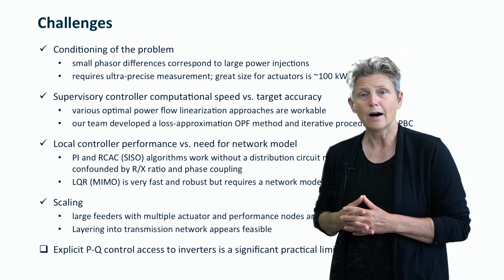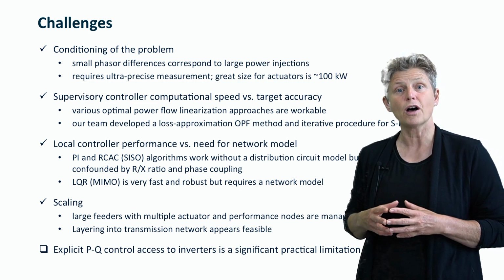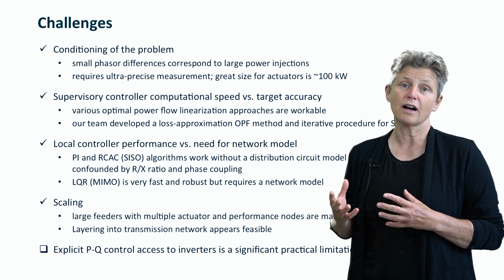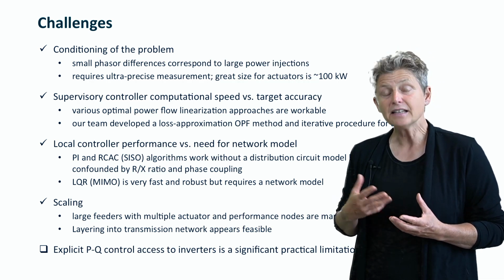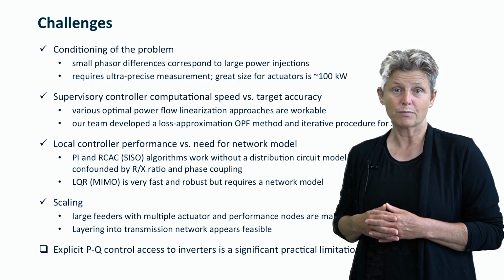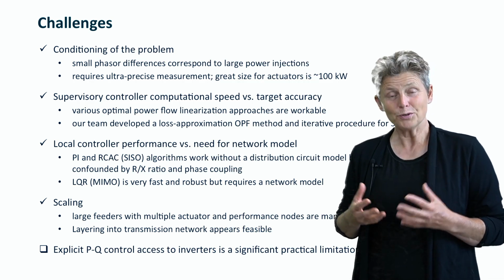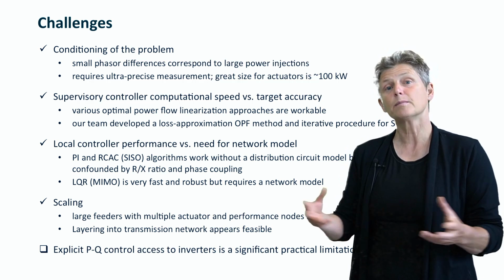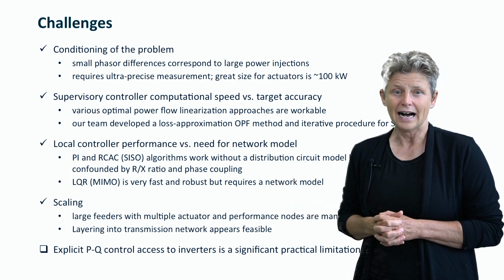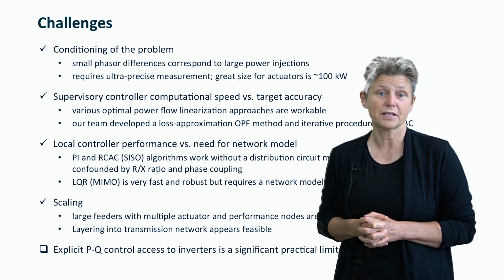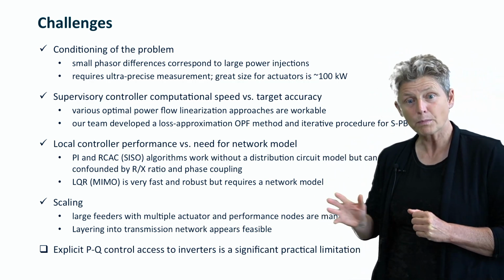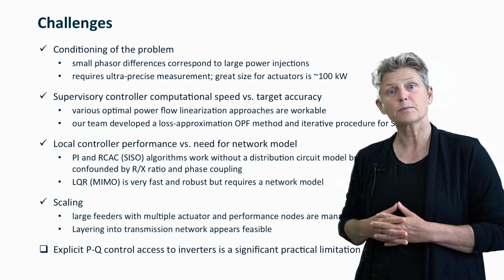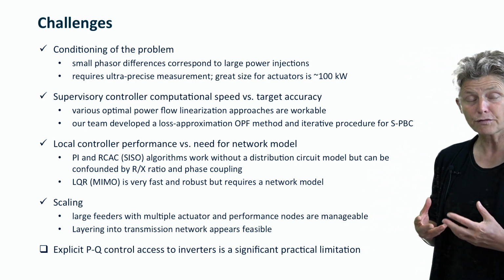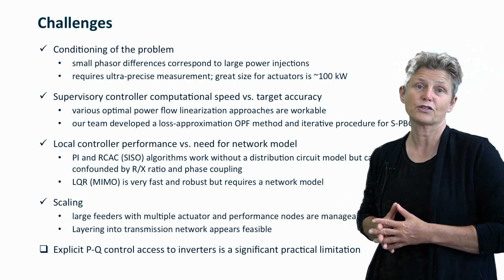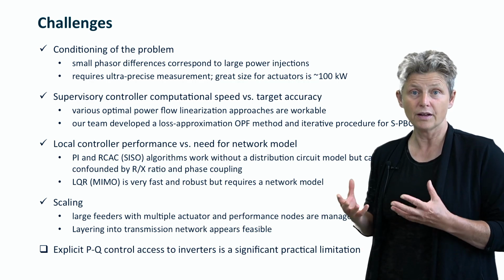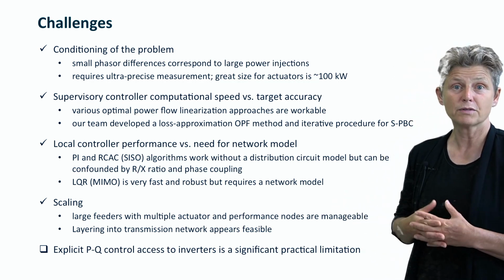We've also worked with the supervisory control optimization to see how we can trade off speed versus accuracy in a linearization of the optimal power flow problem. That can take a long time to compute if you do it very accurately and very carefully, depending on how large a system you're dealing with. So we actually developed some techniques for taking appropriate shortcuts, including a loss approximation power flow, and an iterative procedure for essentially arriving at the solution that will give us close enough to the operating state that we're looking for in a reasonable amount of time.